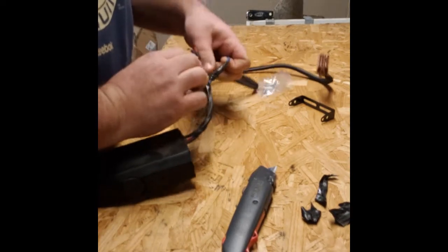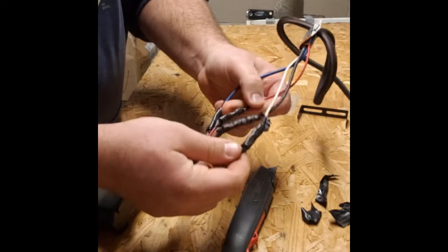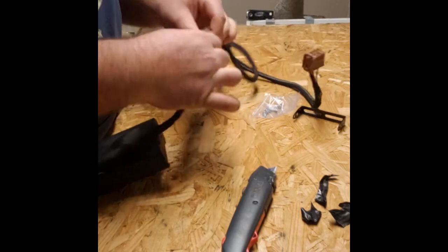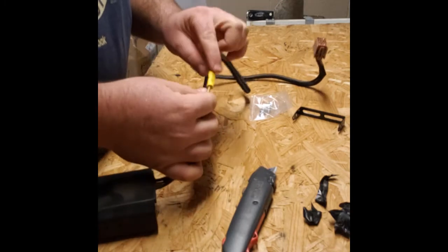As I always tell you guys, there's something about having pride in your work. This guy here looks like he took crimp connectors and just went crazy with the electrical tape after the fact. Probably not the best way to do this. Yeah, in fact, sometimes people don't even hit these crimp connectors. And actually, this isn't even the right size crimp connector.